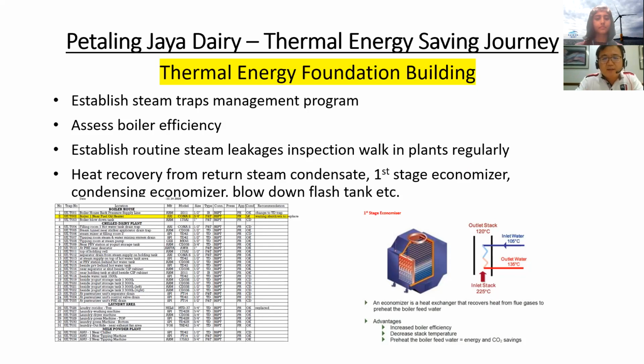This is important, and how we do it is we set KPIs for our subordinates and let them start working on the habits. Going back to what I said earlier, every plant has its own characteristics and patterns. If the plant is not running on weekends, for example, staff can walk in the plant, because if all the machines are not running, we can hear and see leakages easily, not only steam leakages, but also water, compressed air, and idling machines if there are any. All these leakages should be addressed using these routine jobs.